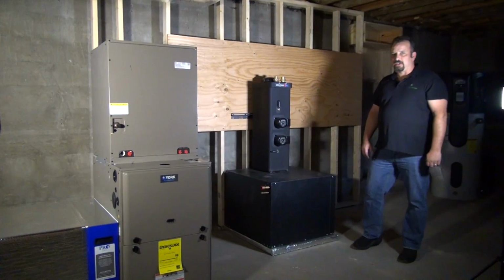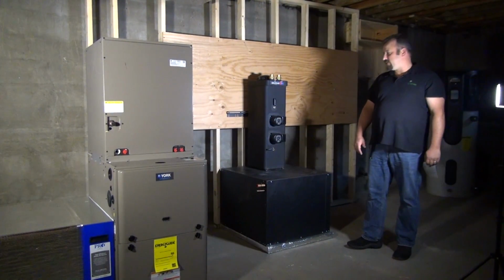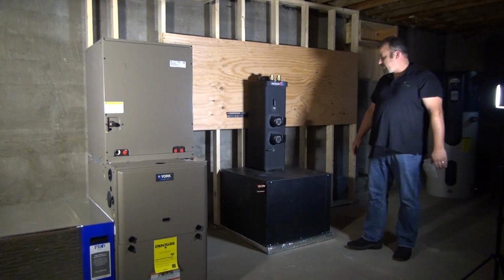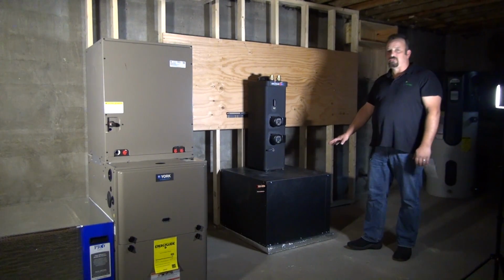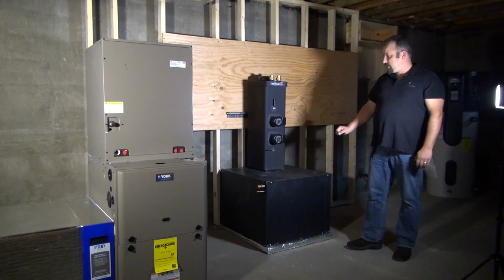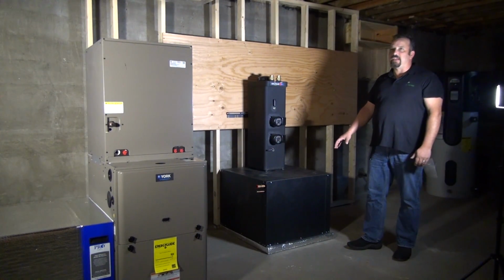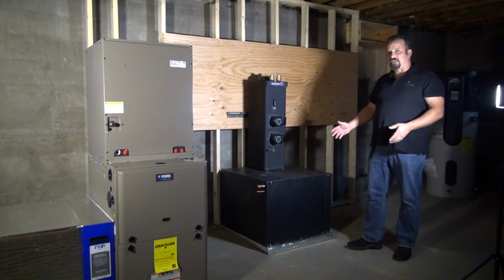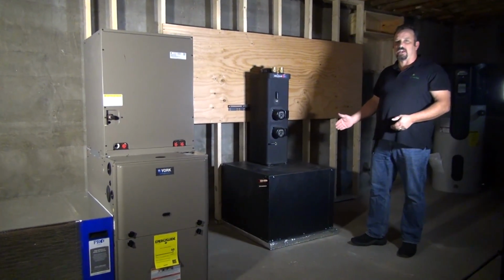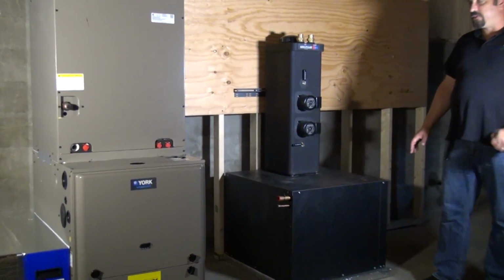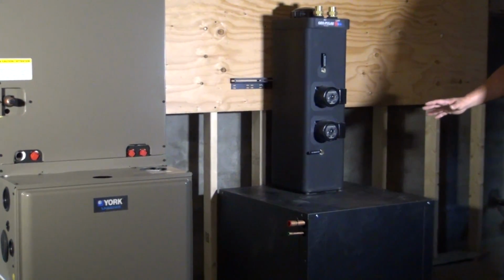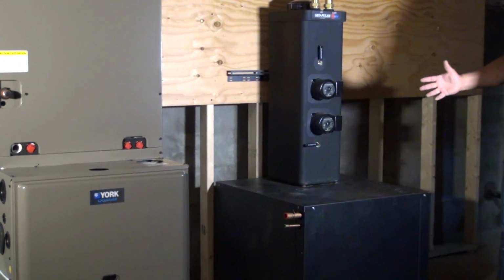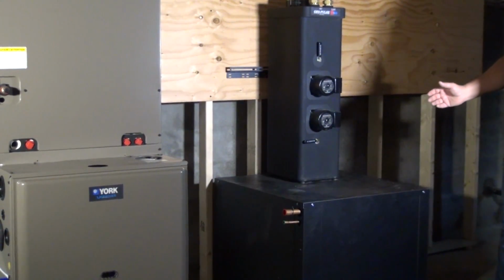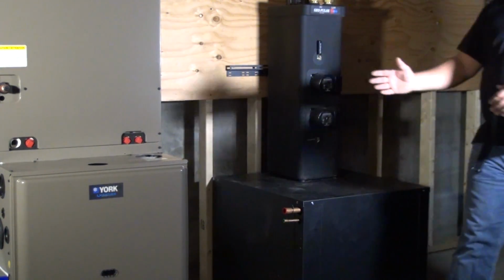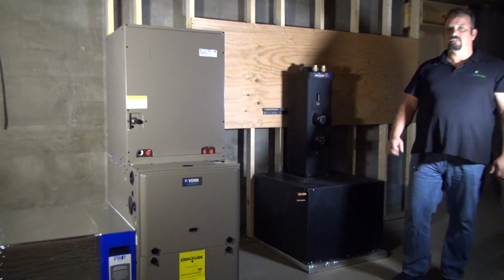Now we're inside here in New Market, and what you're looking at is what they call a split geothermal heat pump. The heat pump contains a compressor, condensing section, et cetera, and a heat exchanger that gets connected to the loop field. This is what takes the energy from the ground in the refrigerant circuit and moves it over to this furnace system.